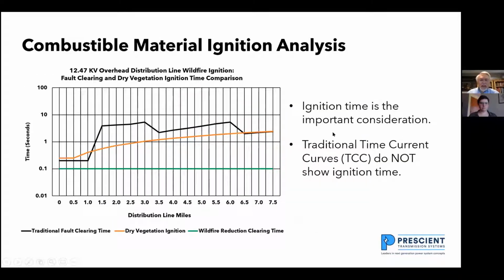And the way we analyze this is we plot ignition time versus distribution line miles. Normally, when you're looking at things like this, our traditional thing is we use time current curves. And time current curves have time on the vertical axis and amperes on the horizontal axis. For wildfire ignition, it's better to use distribution line miles on the horizontal axis and to change the axis from a logarithmic axis to a numerical axis. So on the time, we're still using logarithms. The plot is from 10 milliseconds to 100 seconds, and the distance starts at the substation and goes out to 7.5 miles. On the first mile of the line, I can clear faults using instantaneous relays at the substation.